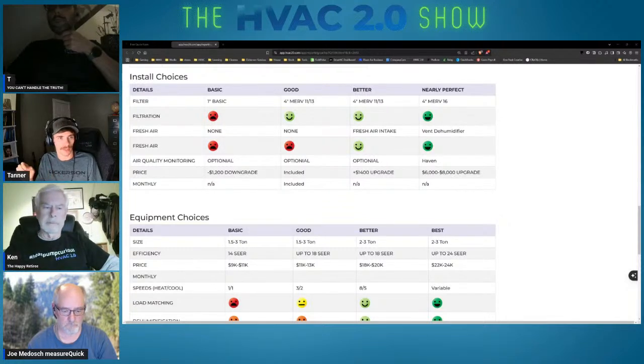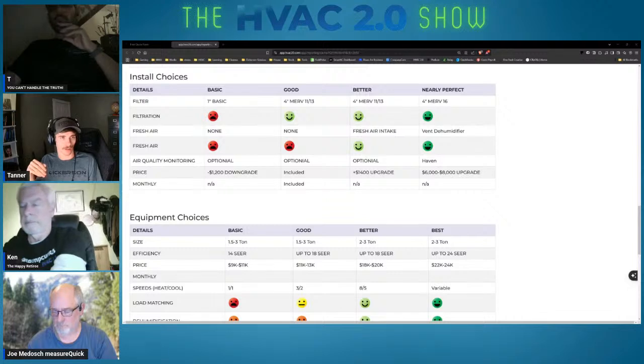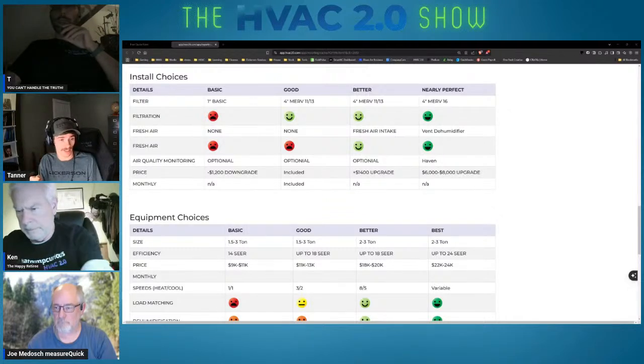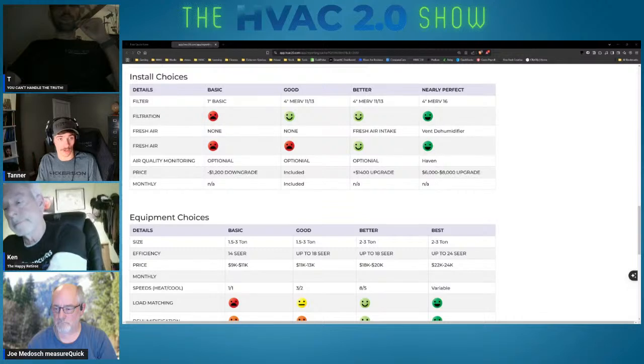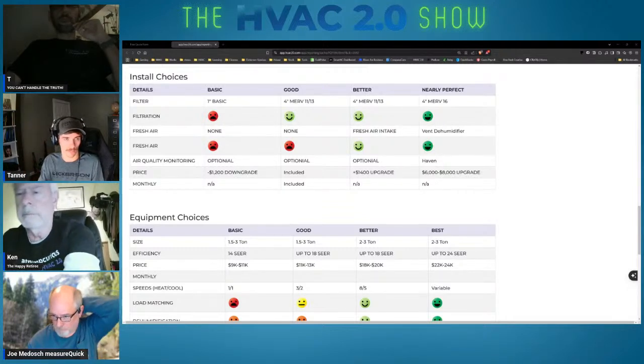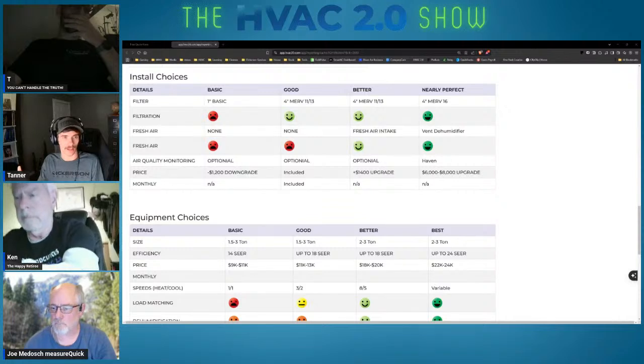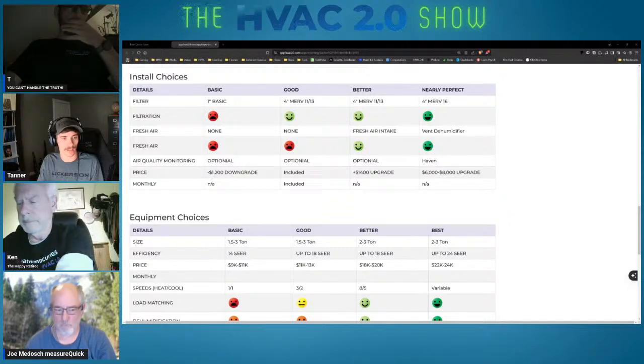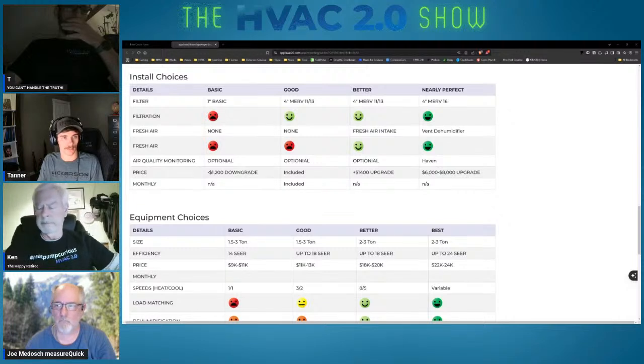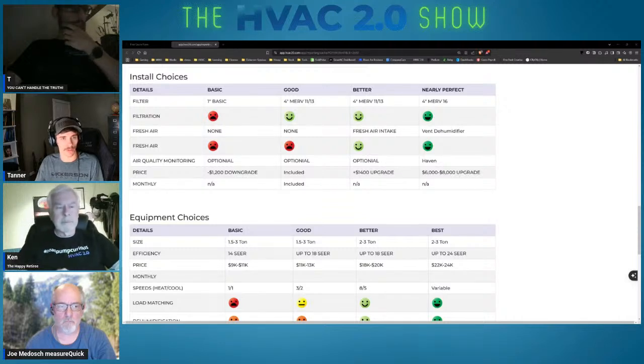Anytime you can slow drip this, the better. So at maintenance calls or whatever, that's when you should be thoroughly testing everything, finding, okay, this 4-ton unit only has 2.5 tons of ductwork. The static pressure is 0.9 to 1 inch, and it's only delivering a fraction of the airflow it should, which means when the system was installed, it wasn't charged properly. Therefore, it's only doing part capacity. You can let them know ahead of time, so when it comes time to replace it, they already know all these looming issues, cutting down on the amount of information you're throwing at them. Being able to do that, if you can, that's best.